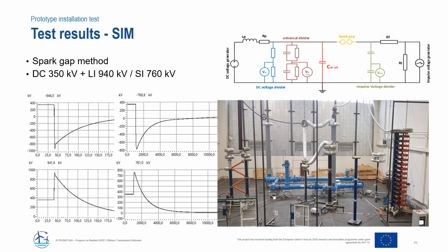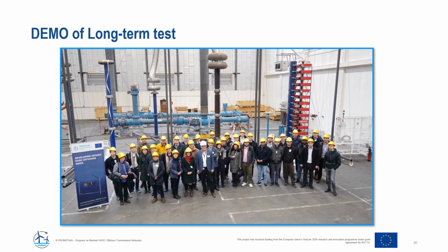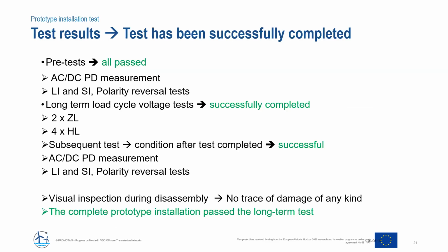And on the left, you see test results. Of course, lightning superimposed onto the DC voltage and switching superimposed onto the DC voltage of both polarities. That's what you see on these graphs. And of course the test circuit is shown on the top right. On many occasions, people are invited to see the test when the test object is live or under stress. It was one of the purposes of promotion to demonstrate to the different stakeholders what's going on, and this photo was taken when a lot of people were invited to take part in a demonstration of HVDC GIS.